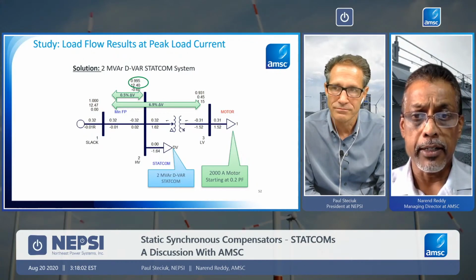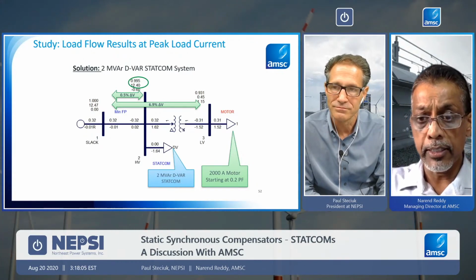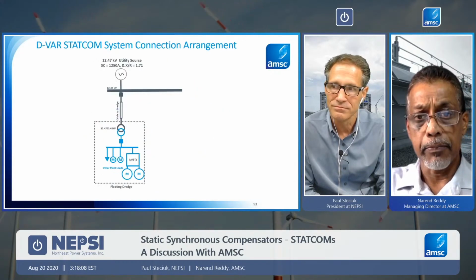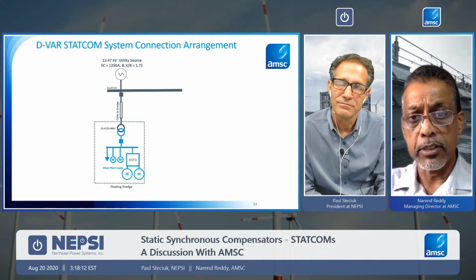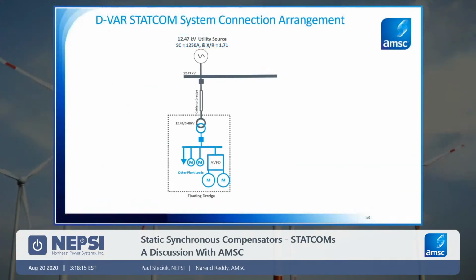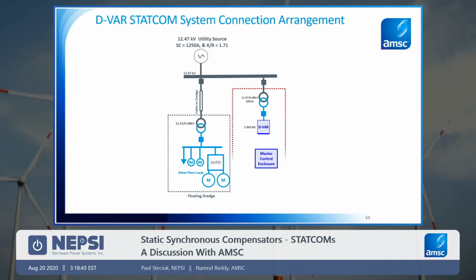So this 2 MVAr D-VAR, we installed that. It is a small device, as I mentioned. It's a configurable device. Now, in terms of the connection arrangement, this is a one-line diagram of what the facility service is. You have a 12.47 kV utility supply, then a small short cable, the step-down transformer, and then you have these motors and variable frequency drives. Some of these motors are operated through VFDs as well. In terms of the D-VAR connection, as I mentioned, the D-VAR unit has a 480 volt output. We utilize a step-up transformer to connect it to medium voltage, and in this case it's a 12.47 kV primary transformer.